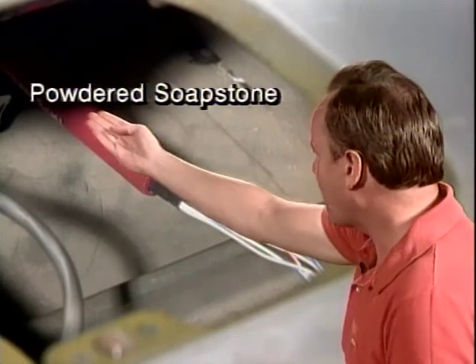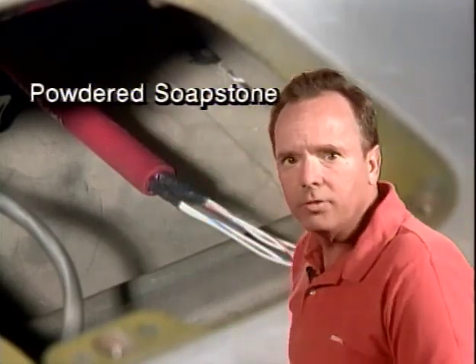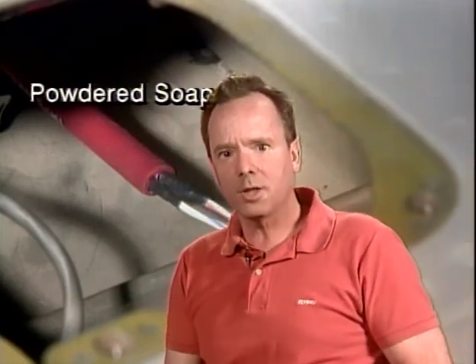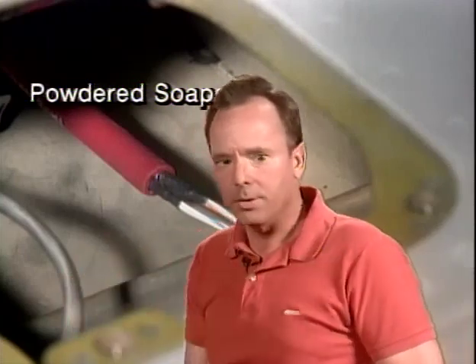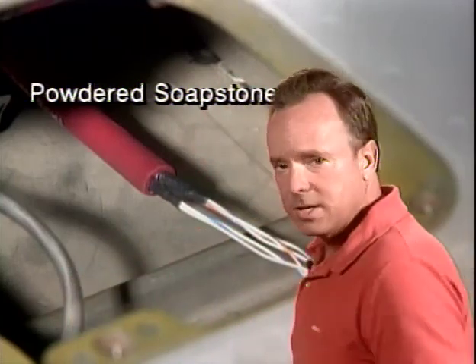Now, if you have several long lengths of electrical cable and they're being installed in a rigid conduit, how are you going to do it? And the answer is to dust the cable with powdered soapstone to reduce the possibility of damage to the cable as it's pulled through the conduit. Powdered soapstone is basically a lubricant for electrical cables.